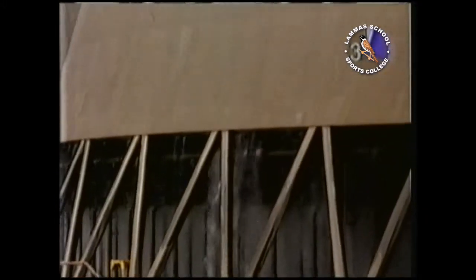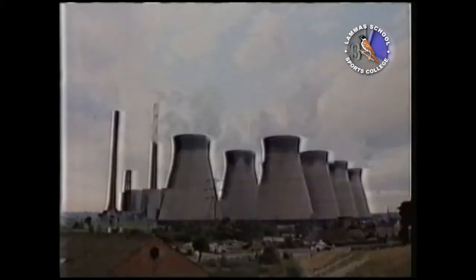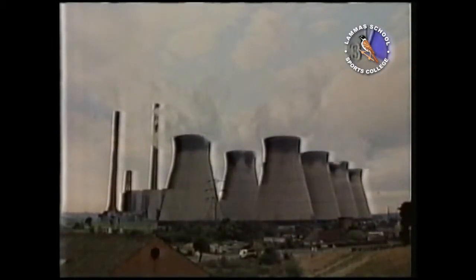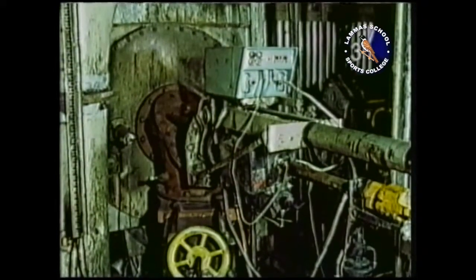But a power station can only transfer about a third of the energy of the fuel. That's not because a modern power station is by its nature inefficient or badly operated. It's because there's a fundamental law of nature which tells us that if we try to change energy from heat energy into mechanical energy, and therefore into electricity, we can't do much better than that with modern technology. It's the temperature of the steam, essentially, which determines the ultimate efficiency of the power station. And the highest temperature you can go to with that steam depends on things like materials.